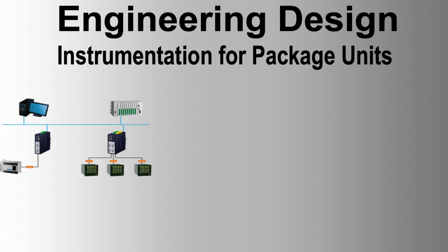The contractor shall specify the amount and type of data that will be transmitted to the DCS, together with the required faceplates, graphics, trends, etc., which shall be made available on the DCS operator interface. The equipment package vendor shall configure his system for transmitting the specified amount and type of data and work out with the DCS vendor how the data will be received, together with the required presentation format at the operator interface.